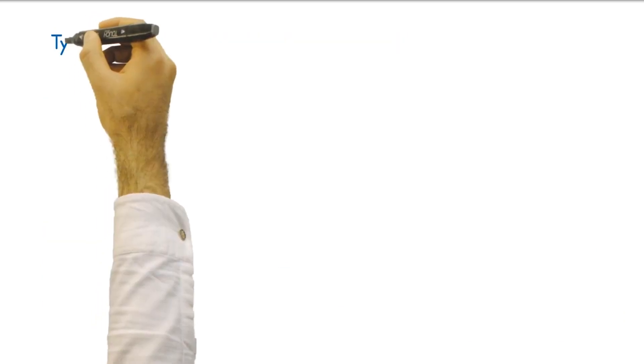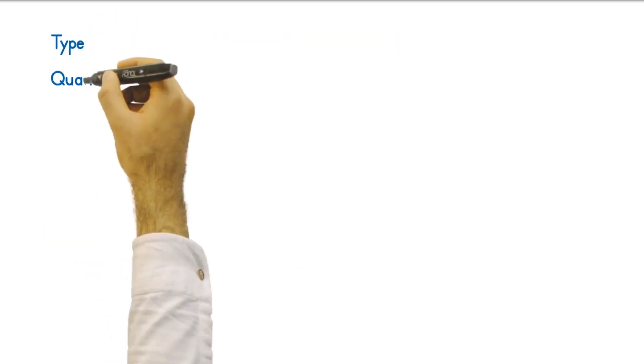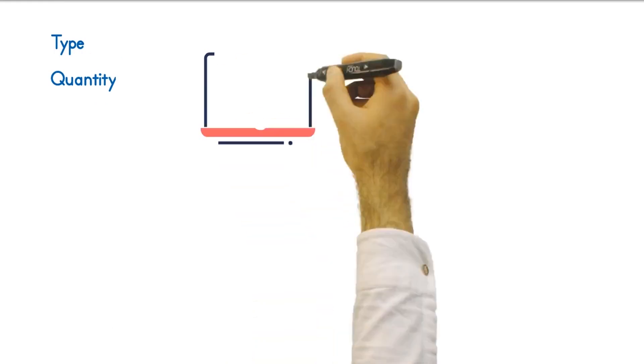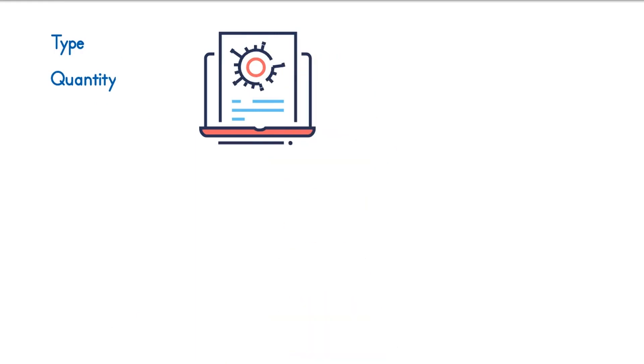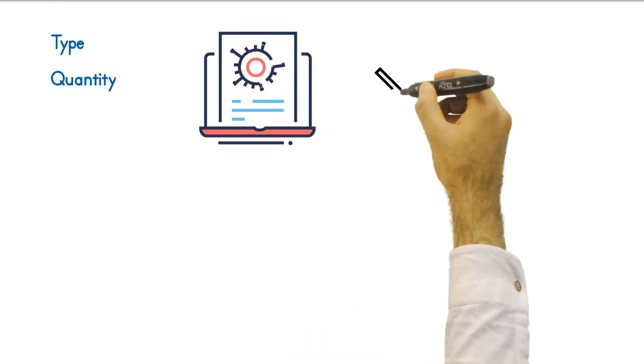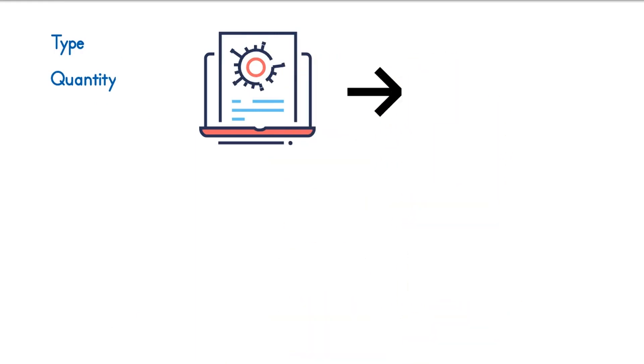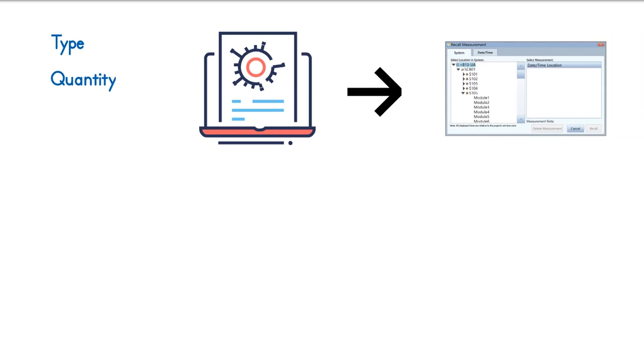Before performing IV curve tests, determine the type and quantity of modules that are connected in the string. This information and other data are entered into the software, and the PV installation structure is created, usually in the form of a systemization tree.